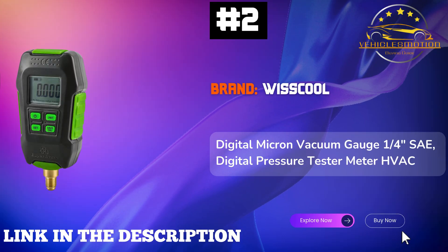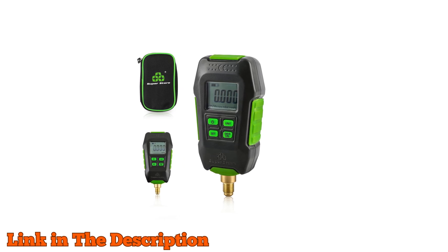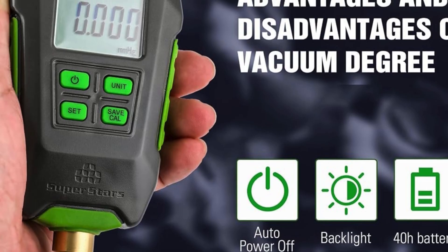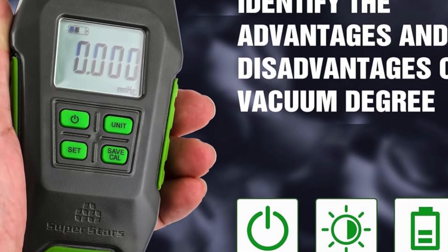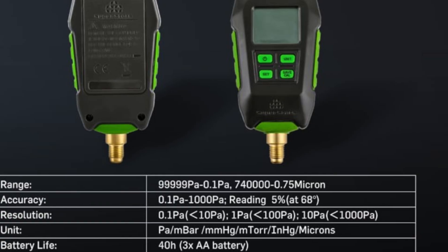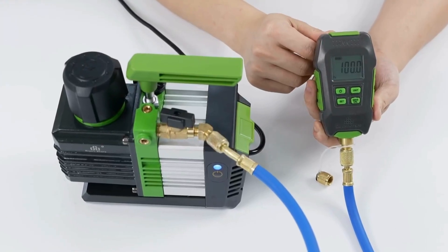Number 2: WissCool Digital Micron Vacuum Gauge. This incredible pressure tester meter for HVAC professionals is designed for accuracy, boasting a remarkable measurement range of 99,999 to 0.1 pascals, or 740,000 to 0.75 micron, and an accuracy of plus or minus 5% at 20 degrees Celsius. Featuring a high-performance Pirani vacuum sensor, this gauge ensures rapid results. Versatility is at your fingertips with six conversion units available — Pa, MBAR, MMHG, MTorr, InHg, and Microns — allowing you to switch between units effortlessly as needed.